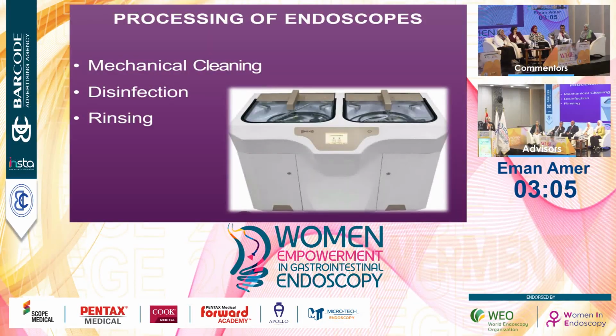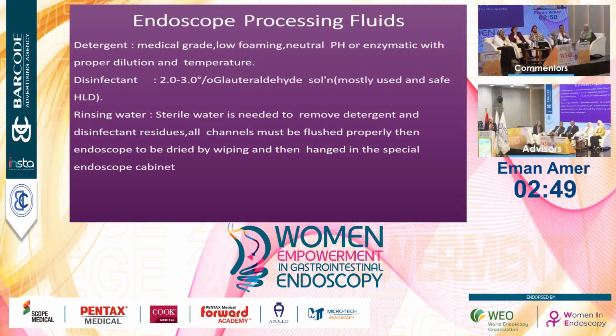How we are going processing of the scope: mechanical cleaning, disinfecting, and rinsing. Every physician, before working with patients, should know the scope, how it works, how to use it, and how to deal with it, even the disinfection. So in the scope processing fluids, we use detergent, medical grade low foaming neutral pH, or enzymatic with proper dilution and temperature. Disinfectant like glutaraldehyde, mostly used and safe. Rinsing water, sterile water is needed to remove detergent and disinfectant residuals. All channels must be flushed properly. Then the endoscope is to be dried by wiping, and then hung in a special endoscope cabin.